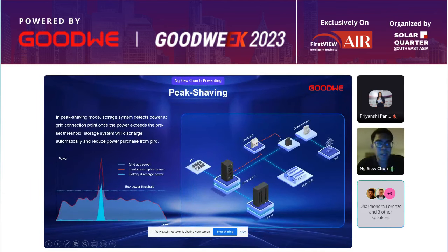Then the next part would be the peak load shaving module. This algorithm is also integrated into our storage system. Basically, clients could set the maximum demand threshold via the app. Once the incoming power purchase from the grid hits or exceeds this pre-configured threshold, our battery system will automatically discharge power to compensate or reduce the maximum demand from the grid. By that, we are able to control the maximum demand surcharge that will be charged by the grid.